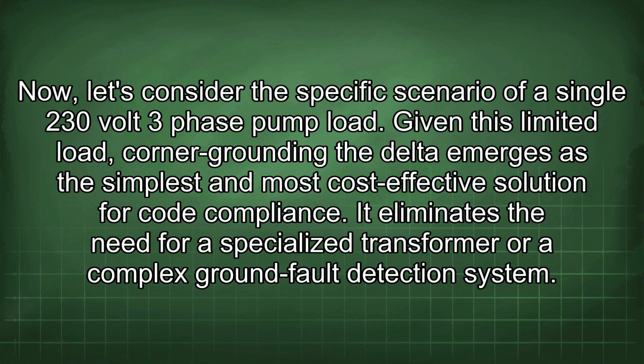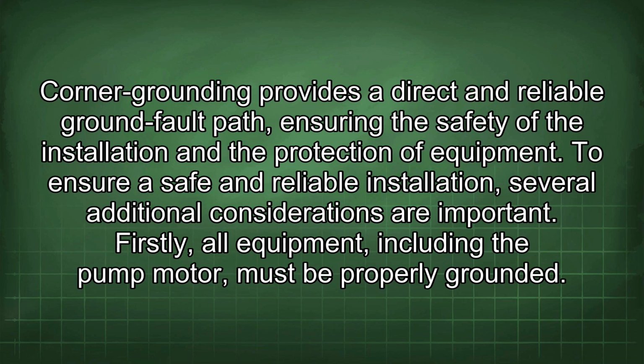Given this limited load, corner grounding the delta emerges as the simplest and most cost-effective solution for code compliance. It eliminates the need for a specialized transformer or a complex ground fault detection system. Corner grounding provides a direct and reliable ground fault path, ensuring the safety of the installation and the protection of equipment. To ensure a safe and reliable installation, several additional considerations are important.